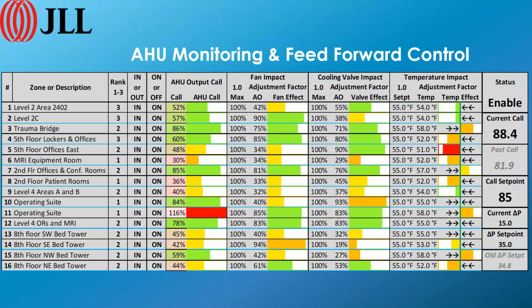There's some issue with the cooling valve, or we look at the cooling valve impact. What is the valve position, and also what is the temperature of that air handler? So if things are happening in the zones and it's starting to affect what's going on with the air handler, that tells this system, hey, there are some things that we need to do to make changes in the delta P set point for the chilled water loop.